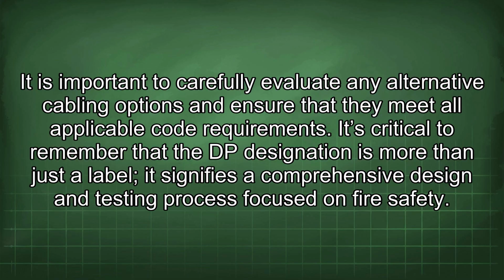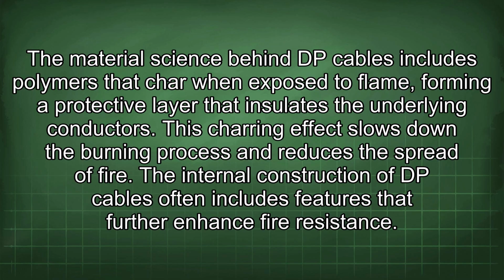It's critical to remember that the DP designation is more than just a label. It signifies a comprehensive design and testing process focused on fire safety. The material science behind DP cables includes polymers that char when exposed to flame, forming a protective layer that insulates the underlying conductors. This charring effect slows down the burning process and reduces the spread of fire.